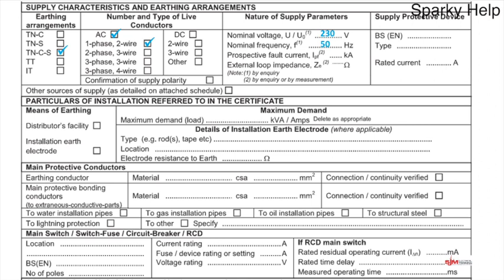It's prospective fault current, next one down, it's got number 2 next to it, and that's got by enquiry or by measurement. Now we could do by enquiry, and you would contact the electricity company if you didn't have the paperwork to hand from the designer, and they would quote you the maximum available for your earthing system compared to your incoming supply, and they will always quote you the biggest figure available. It is probably unlikely to be anywhere near that, so it might be best to measure it. I have done a video on producing this, and there's a QR code that would take you to it.